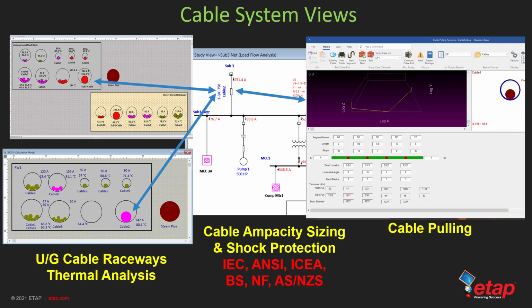You can also do the cable pulling for the same cable you did the thermal analysis. You can do the cable pulling and get the maximum or minimum tensions or both ends, forward or reverse pull, or the sidewall pressures at different locations and the bend, and it has no limitation as to the slope and the angle of the different bends.